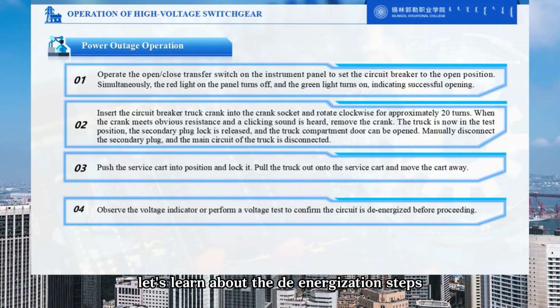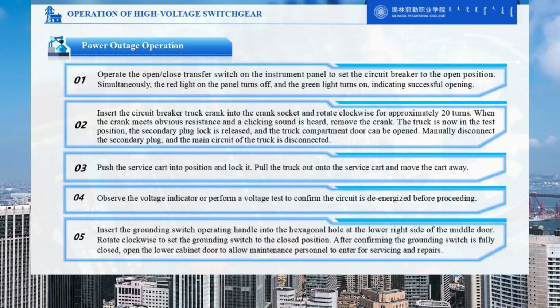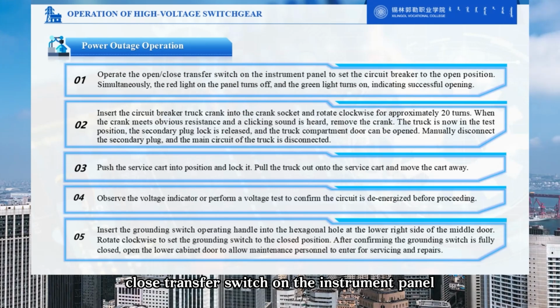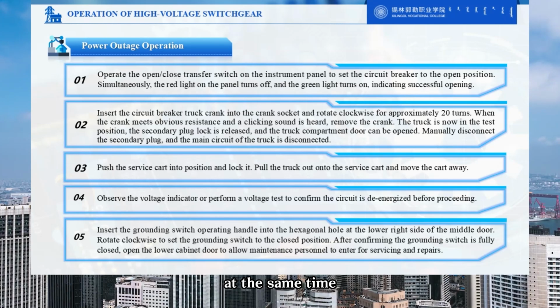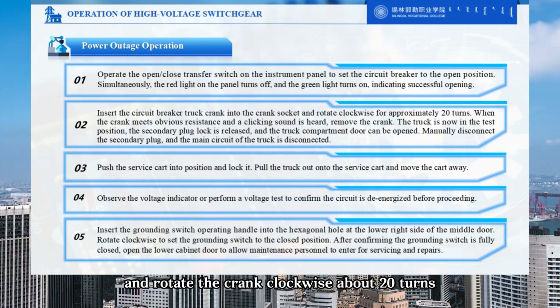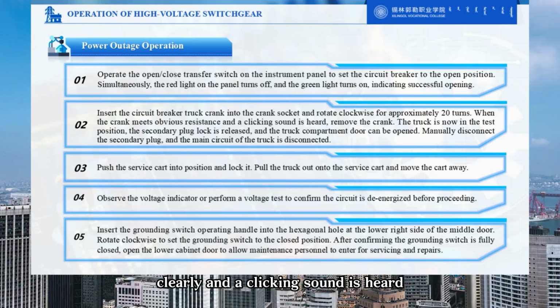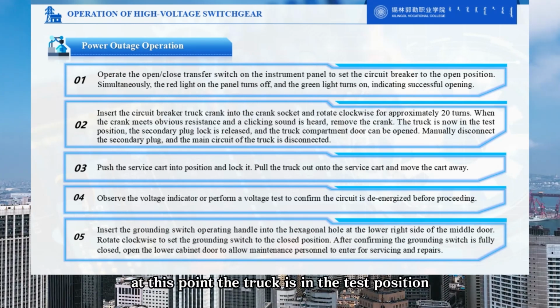Next, let's learn about the de-energization steps. For high-voltage switchgear, operate the open/close transfer switch on the instrument panel to set the circuit breaker to the open position. At the same time, the red light on the instrument panel turns off and the green light turns on, indicating successful opening. Insert the circuit breaker truck crank into the crank socket and rotate the crank clockwise about 20 turns until the crank is clearly in place and a clicking sound is heard. Remove the crank. At this point, the truck is in the test position. The secondary plug lock is released.